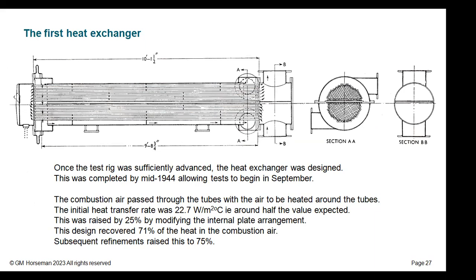Now, remember, Parsons is coming from a steam turbine background, and unsurprisingly, the heat exchangers look like steam turbine feed heaters. Again, it's a tube and shell heat exchanger, so there's no reason for why not, except using air, which is largely not much above atmospheric pressure. The heat transfer coefficient with air is much lower than with steam, so there is a challenge there.